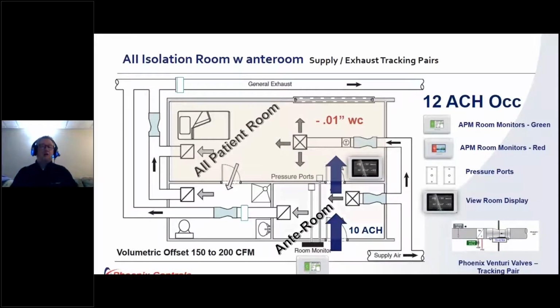When you look at the diagram of an isolation room, basically what we use from a Phoenix Venturi standpoint is what we call a tracking pair. You have an exhaust valve tracking the supply for these two spaces, the ante room and the isolation patient room. And that directional pressure has to go from the public corridor through the ante room and cascade through the patient room, right? All maintaining that negative direction of at least 0.01 inches of water column. Now again, tracking pair, exhaust tracking the supply, maintaining an offset, right? So that volumetric offset typically falls between 100 to 200 CFM under the door. Again, maintaining that direction, isolating that space, isolating that patient, reducing any kind of transmission of outbreak out into the public corridor.